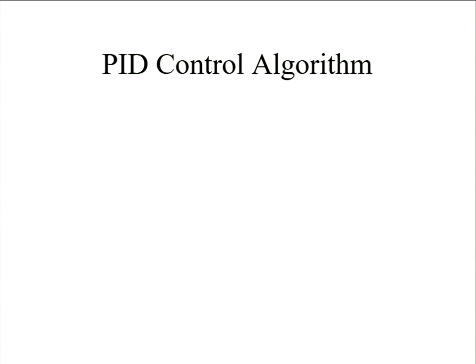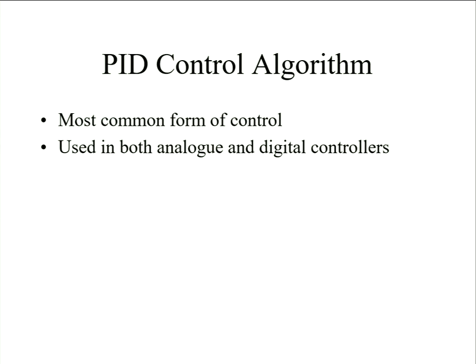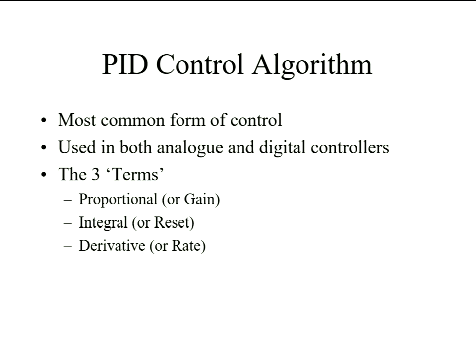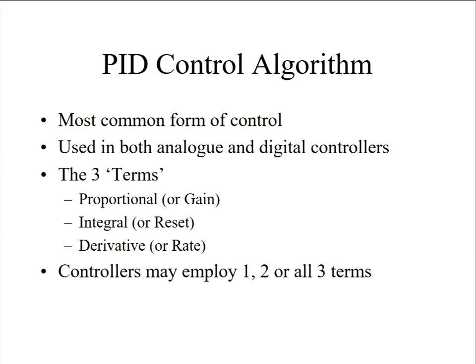And we've got the three terms. P is proportional. We'll say more about each of these terms and build up the algorithm. Sometimes you'll talk about different phrases: gain, proportional band, integral, or sometimes reset control, derivative or rate control. You may use one, two, or all three of these, depending on the nature of your process, and they all contribute something to the nature of the control. So proportional control is the easiest one. It's simple, direct amplification. What was my error? Multiplied by a number, that's my output.